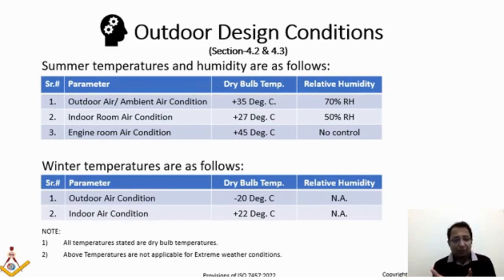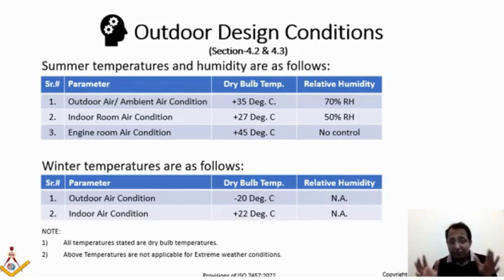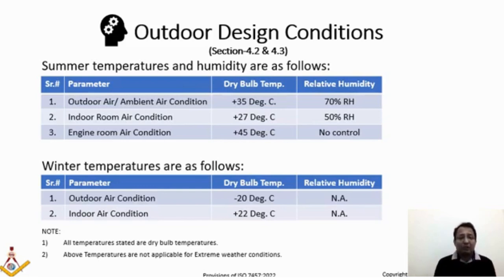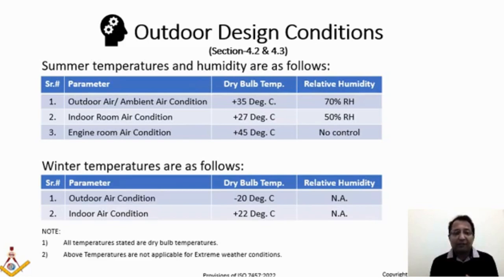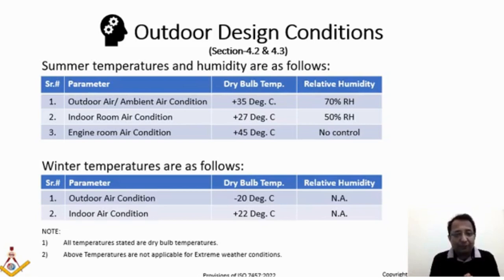The summer outdoor ambient condition is plus 35°C and 70% RH. The indoor room condition to maintain is 27°C and 50% RH. The engine room condition is 45°C with no control of relative humidity. The 10-degree delta T compared to ambient occurs due to heat dissipated by the engine itself, which is why the engine room condition is 45°C. Engine rooms will always be hotter than subsequent rooms.